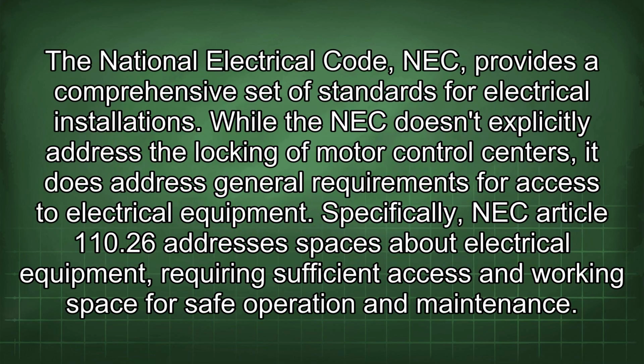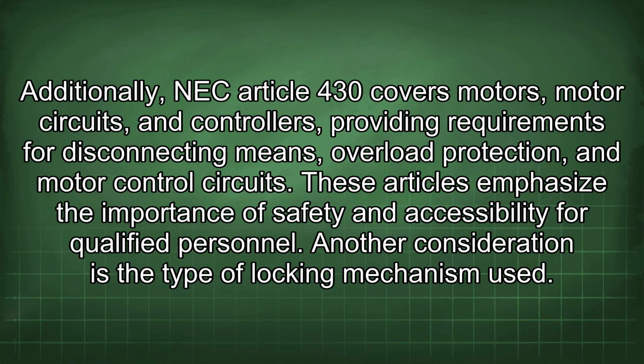The National Electrical Code, NEC, provides a comprehensive set of standards for electrical installations. While the NEC doesn't explicitly address the locking of motor control centers, it does address general requirements for access to electrical equipment. Specifically, NEC Article 110.26 addresses spaces about electrical equipment, requiring sufficient access and working space for safe operation and maintenance. Additionally, NEC Article 430 covers motors, motor circuits, and controllers, providing requirements for disconnecting means, overload protection, and motor control circuits. These articles emphasize the importance of safety and accessibility for qualified personnel.